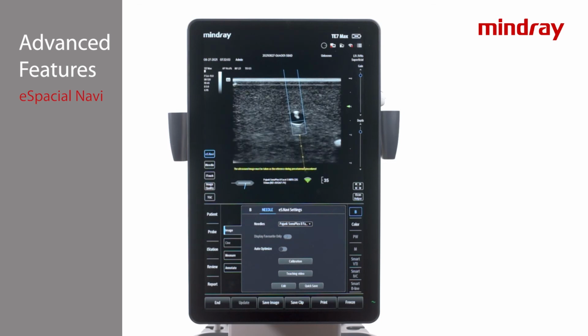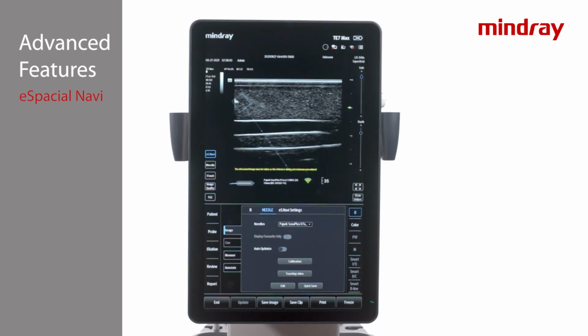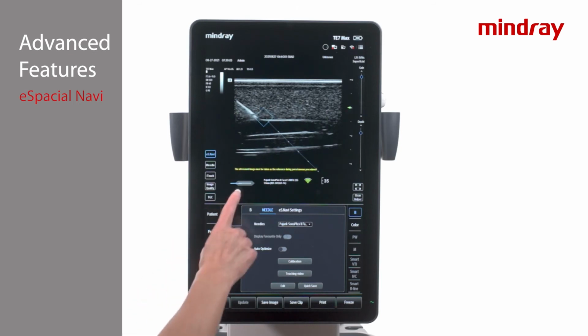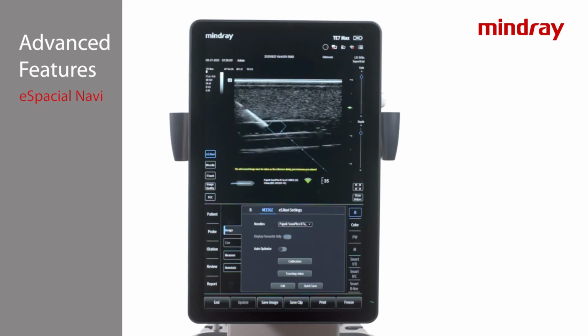Blue indicates the needle is crossing the ultrasound beam, light blue is close to the beam, and orange means the needle has fallen out of the ultrasound beam. For in-plane procedures, the colors mean the same. Once the box is blue, the needle is in plane with the ultrasound beam. Light blue means the needle is close to the beam, and orange has fallen out of the beam. Notice the graphic at the bottom left of the image, which shows the needle orientation in relation to the ultrasound beam.